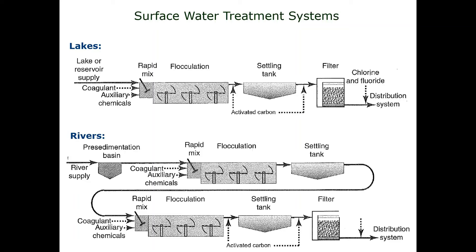Lake water tends to have less clay and sediment because a lake is essentially a giant settling tank. It doesn't mean it doesn't have other things in it, but for the sedimentation part of treatment, lake water usually requires way less alum and sedimentation because it's already kind of done that — depending on where the outtake is. Rivers pick up a lot more silt and clay, and you've got all the geology and other things to consider. Generally, lakes tend to have less solids.